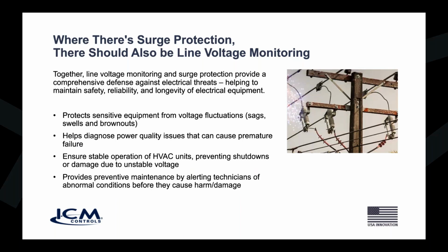But most of the time, what you're going to see is grid level changes, bringing that voltage up to 252, 255 volts for an extended period of time. Even if it's not extended, it's still going to take out that mini split board. But your surge protection will see nothing wrong because it's only looking for those very high energy, fast acting spikes. It's not looking for the grid level change.